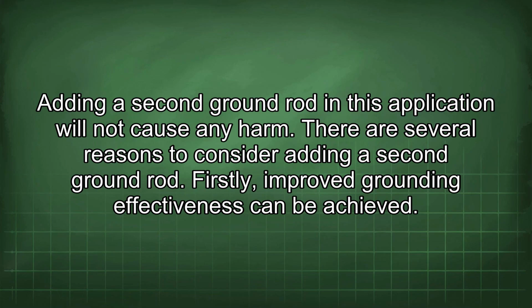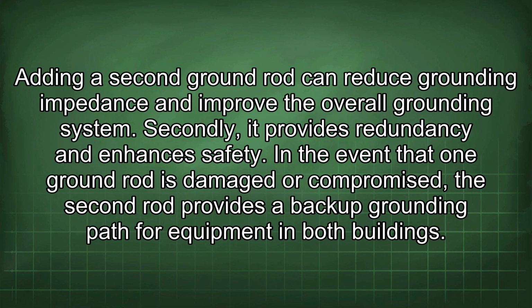Adding a second ground rod in this application will not cause any harm. There are several reasons to consider adding a second ground rod. Firstly, improved grounding effectiveness can be achieved. Adding a second ground rod can reduce grounding impedance and improve the overall grounding system. Secondly, it provides redundancy and enhances safety.